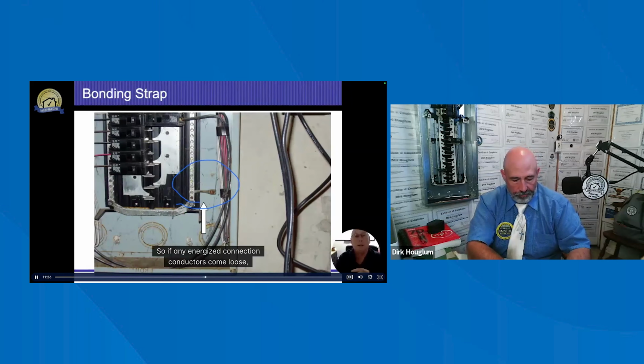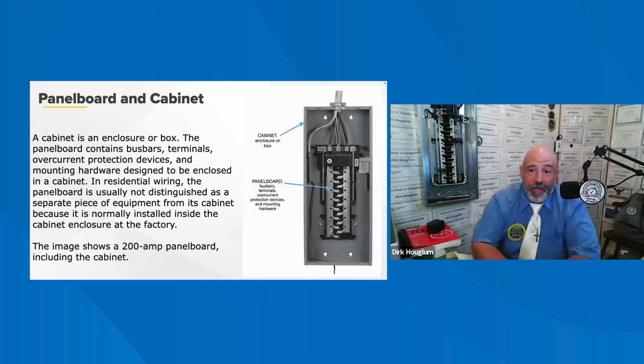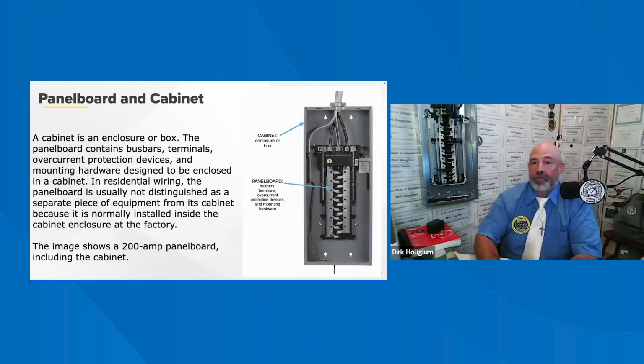So if any energized conductors come loose and energize my box, then that's going to go ahead and energize my neutral wire. Most electrical panels used in a single-family or two-family home come with a factory bond already built into the metal cabinet. In the article, NEC 312.2, they say panel board. I'm talking about both the panel and the cabinet together. They have to be bonded accordingly.